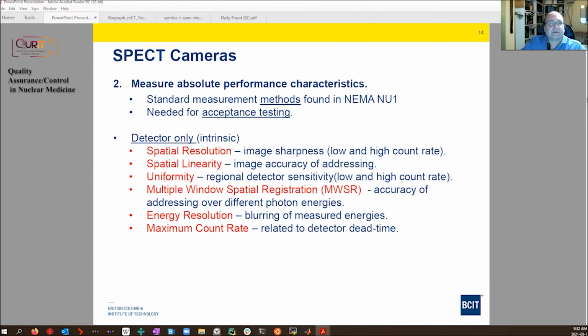And so the types of tests that are done are measuring resolution, which is the sharpness of the image. Linearity, as I said, is the accuracy of the addressing. It's shown by whether a line of radiation produces a line in the image. Uniformity is a uniform response, so that a uniform flood of radiation on the detector produces a uniform count density.